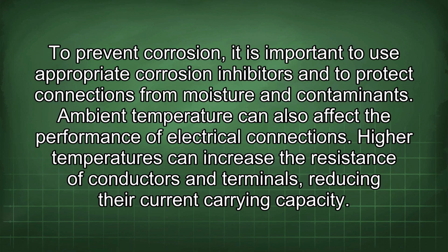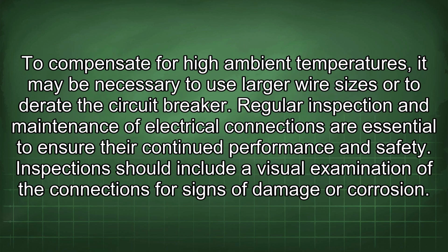To prevent corrosion, it is important to use appropriate corrosion inhibitors and to protect connections from moisture and contaminants. Ambient temperature can also affect the performance of electrical connections. Higher temperatures can increase the resistance of conductors and terminals, reducing their current carrying capacity. To compensate for high ambient temperatures, it may be necessary to use larger wire sizes or to derate the circuit breaker. Regular inspection and maintenance of electrical connections are essential to ensure their continued performance and safety.